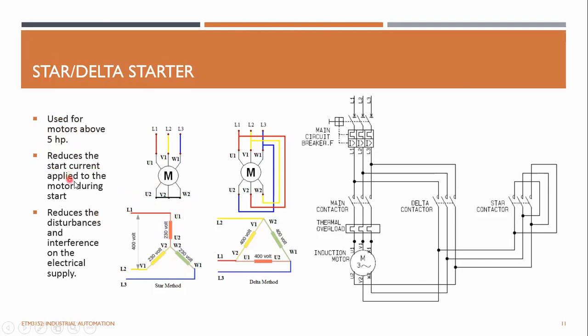It reduces the starting current applied to the motor during the start, and also reduces the disturbance and interference on the electrical supply. When a large current flows at first, it is really disturbing to the main supply, and there could be effects on other circuits. You can see the lights get dimmed and so on, so it is not good.